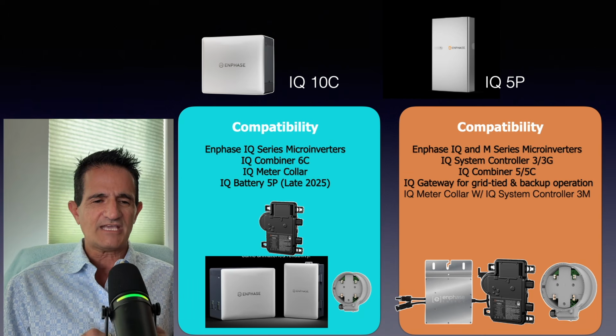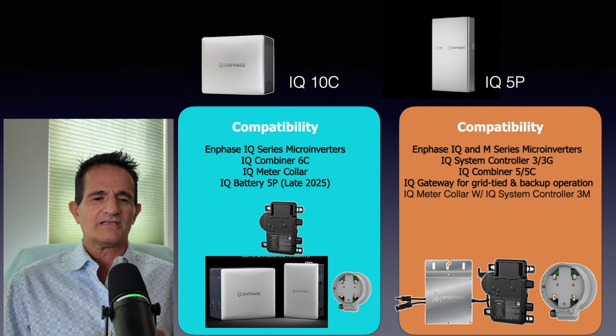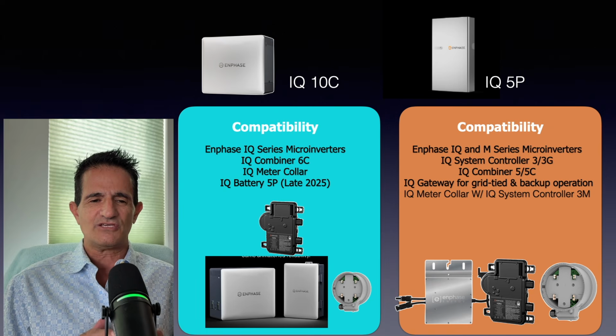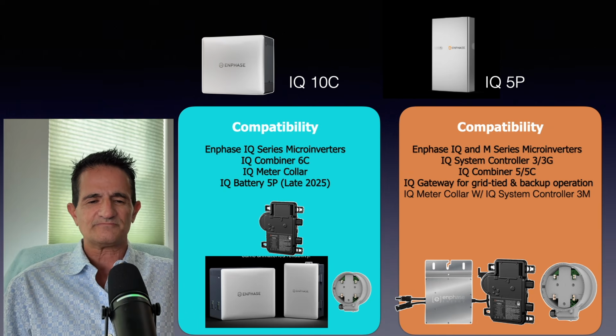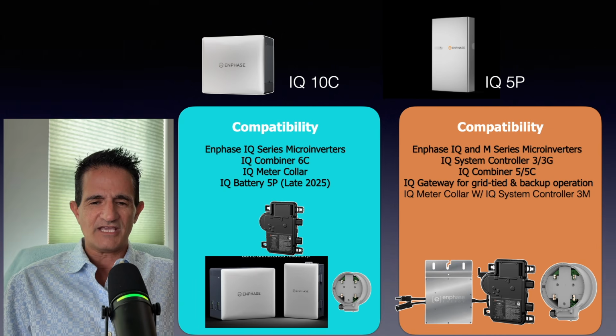For the IQ 5P, that's compatible with the IQ and M series microinverters, the IQ System Controller 3 or 3G, and the Combiner 5 or 5C, and the IQ Gateway for grid-tied and backup operation. Also, you can use the IQ Meter Collar with the IQ System Controller 3M. So the IQ 5P is more backward compatible, is what I'm saying.